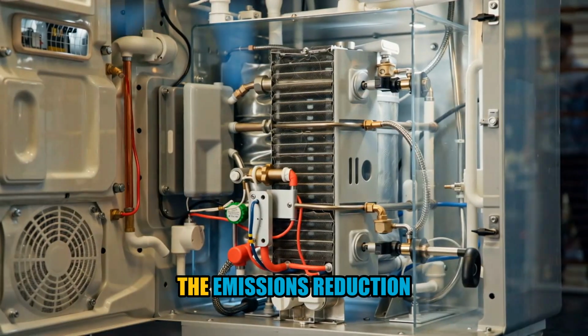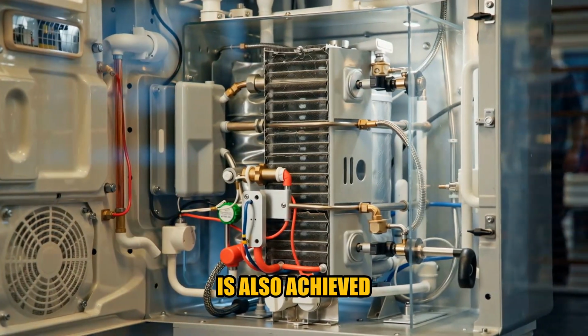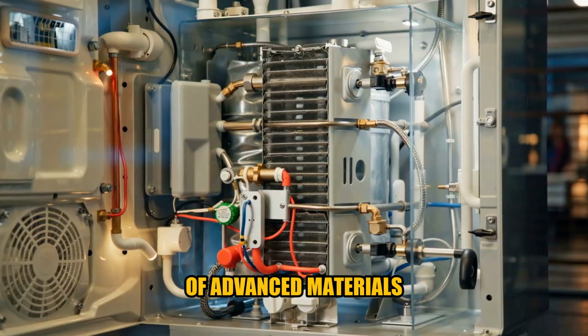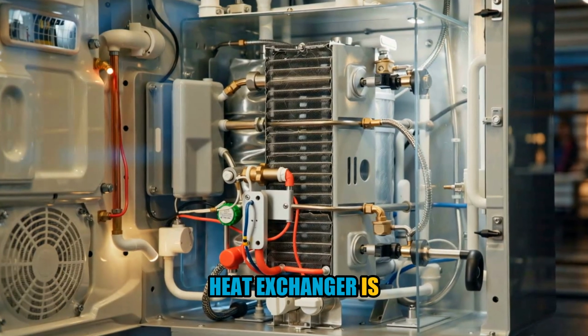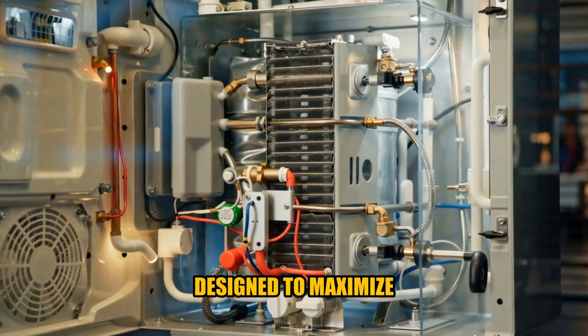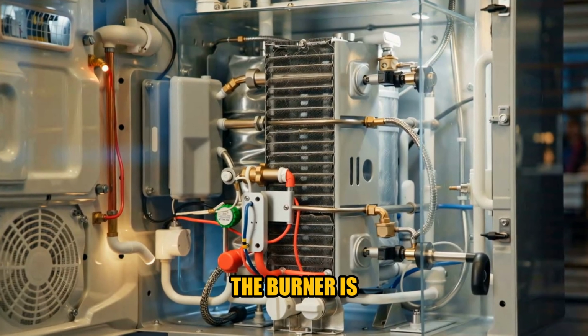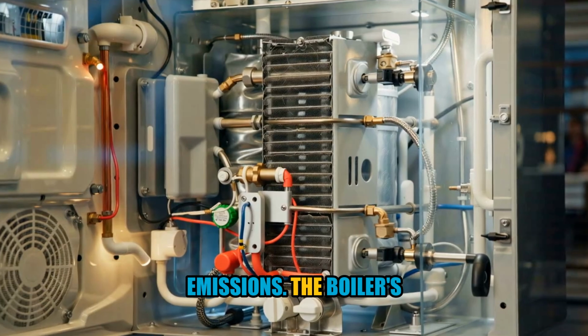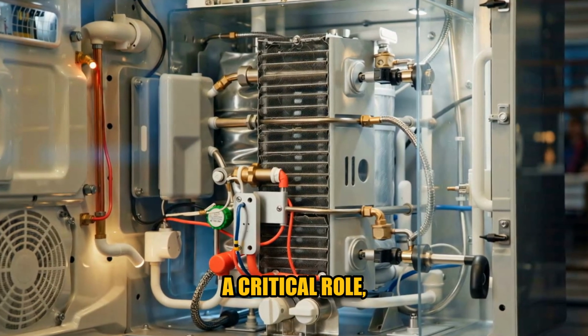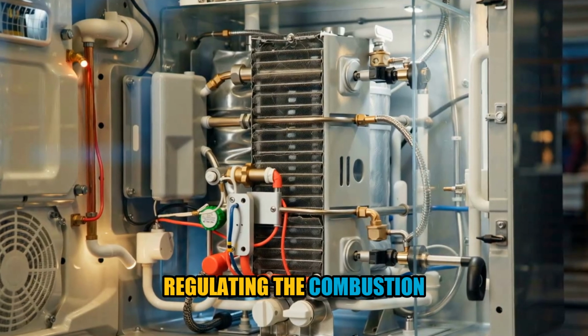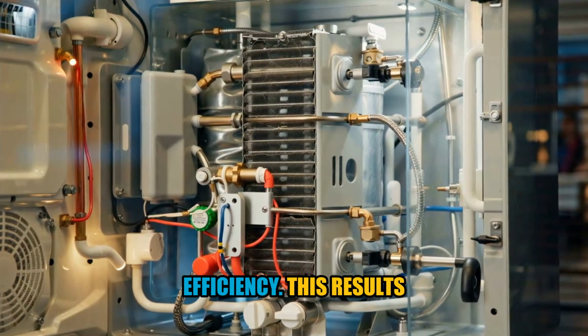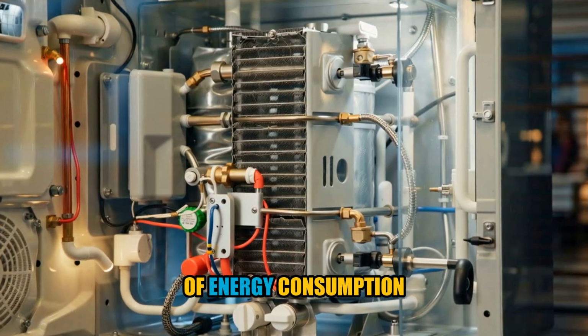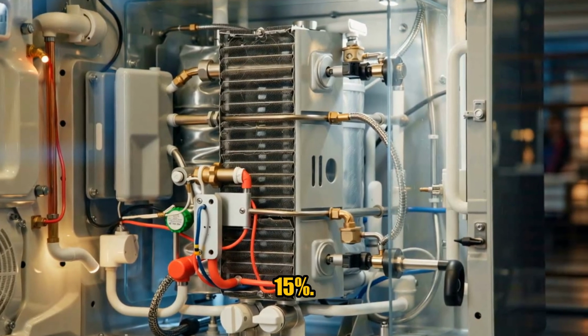The emissions reduction in condensing boilers is also achieved through the use of advanced materials and designs. The heat exchanger is designed to maximize heat transfer, while the burner is designed to minimize emissions. The boiler's controls also play a critical role, regulating the combustion process and optimizing efficiency. This results in a reduction of energy consumption by up to 15%.